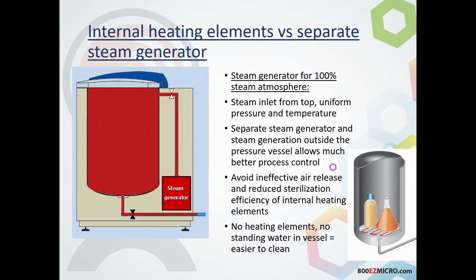So again, internal heating elements versus a separate steam generator. So with the separate steam generator, we're going to be able to completely push steam through the entire instrument. So the steam inlet is from the top with the air release at the bottom. Air is actually heavier than steam.